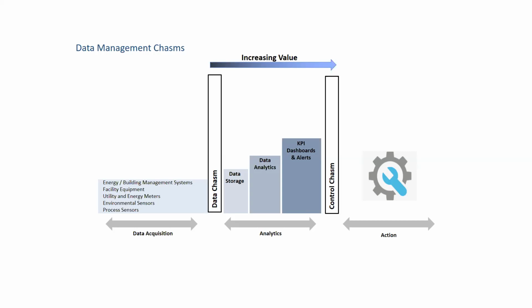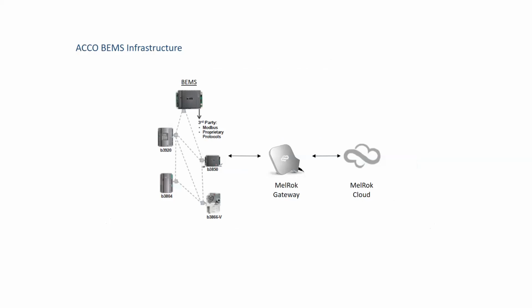The heart and soul of a system like this is really a gateway that's able to connect directly to meters, sub-meters, and BEMS controllers. The trick here is to be able to read and write. With our buildings, the majority had proprietary Infinet, so you could not read and write to them, and we had to map them from proprietary Infinet to BACnet.